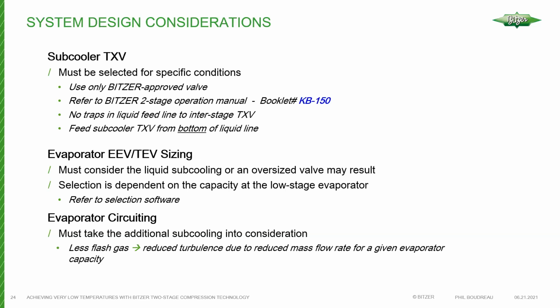And if you don't have a good quality liquid going into that valve, that creates some problems for sure. The evaporator expansion valve, electronic expansion valve or thermostatic expansion valve, whatever is being used, it's very important to consider the liquid subcooling, because when you're subcooling the refrigerant substantially like this, it increases the size of your expansion valve. And if we're not careful, a lot of times you're oversizing a valve anyways, because you pick the closest valve for the application. So you may end up with a valve that's 80% loaded when you design it anyways.